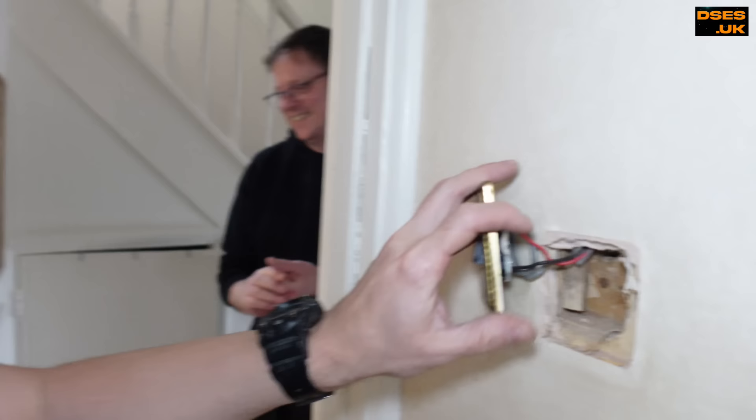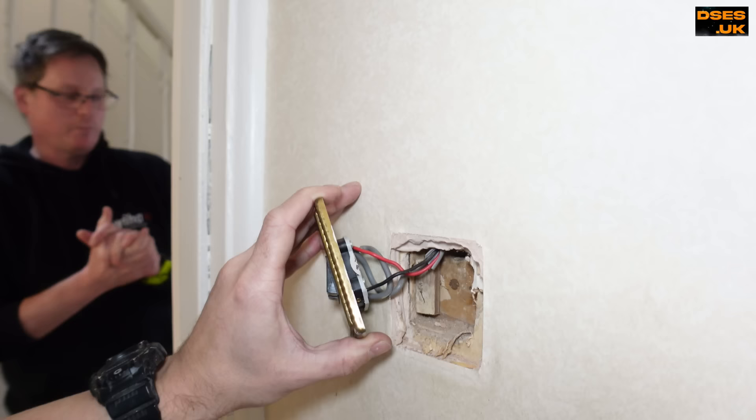We've got these wonderful 1980s style twee granny lights. My parents used to have ones like that - they used to go for all things sort of brass and twee, wanting a country cottage feel even though it's a 1970s semi-detached in Coventry. My wife wants a new light above the table - I'll take one of them. But again, not earthed - there's no earthing on the lighting wiring. Dan is going to be digging out these wooden monstrosities, putting in some metal back boxes and replacing the switches with plastic. Obviously there'll be some decorative damage but they're redecorating anyway.